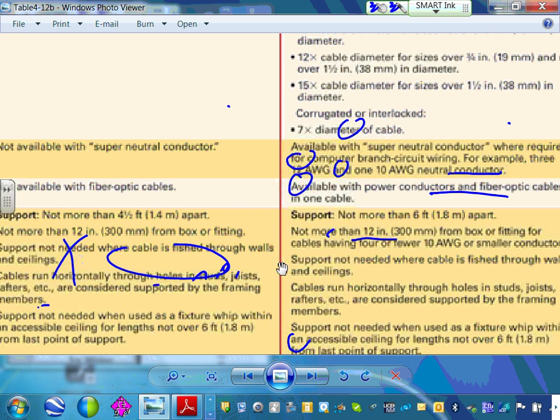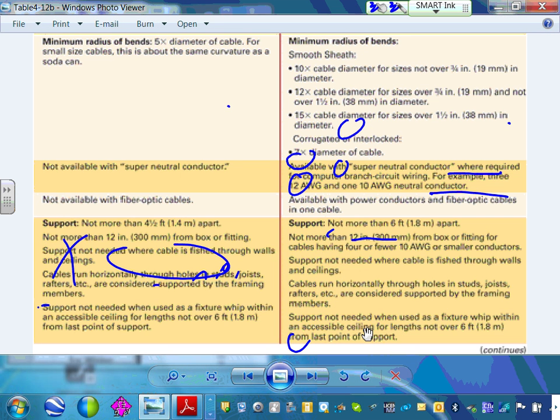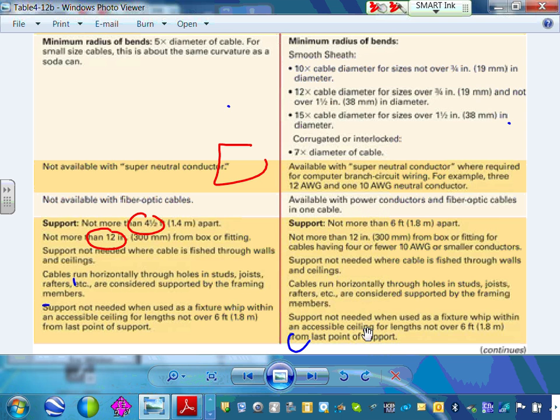Last thing, guys, is support. Look at the support. When you support it, my support is every 3.5 feet. Can you see that? Supporting this cable every 3.5 feet. Support for this guy, 12 inches from every box, every 3.5 feet. So here's my box, 12 inches, and in between the support, 4.5 feet. Okay? That's my support. They can run unsupported if they're fished.